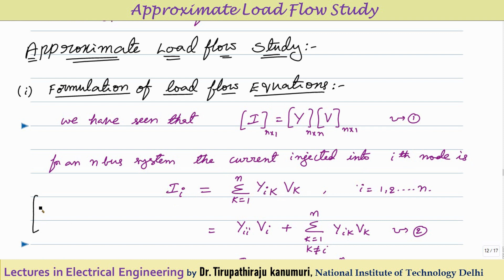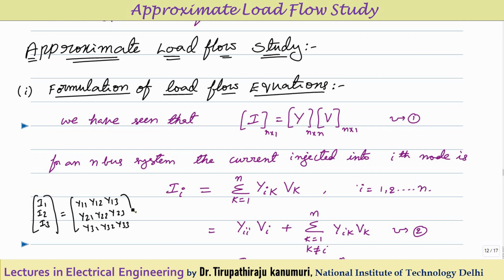Taking the case of a 3-bus system, I can write I1, I2, I3. We have the admittance matrix with elements Y11, Y12, Y13, Y21, Y22, Y23, Y31, Y32, Y33, multiplied by V1, V2, V3. For example, to calculate I2: I2 = Y21*V1 + Y22*V2 + Y23*V3.